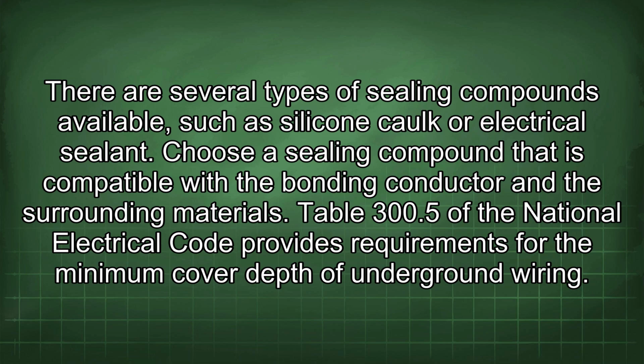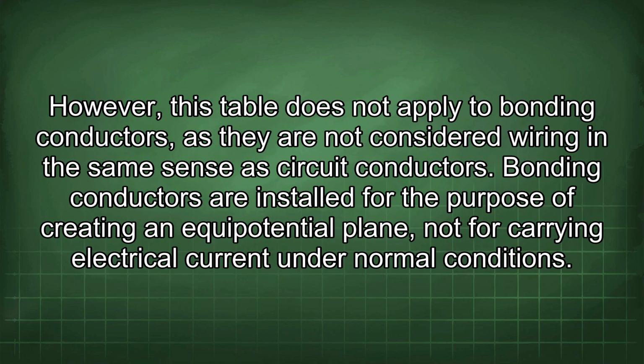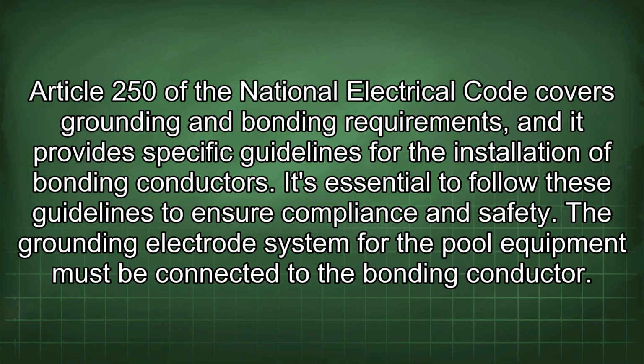Table 300.5 of the National Electrical Code provides requirements for the minimum cover depth of underground wiring. However, this table does not apply to bonding conductors, as they are not considered wiring in the same sense as circuit conductors. Bonding conductors are installed for the purpose of creating an equipotential plane, not for carrying electrical current under normal conditions. Article 250 of the National Electrical Code covers grounding and bonding requirements, and it provides specific guidelines for the installation of bonding conductors.